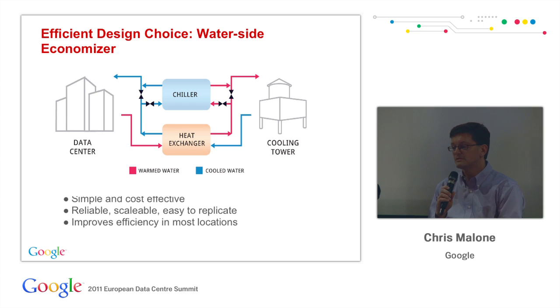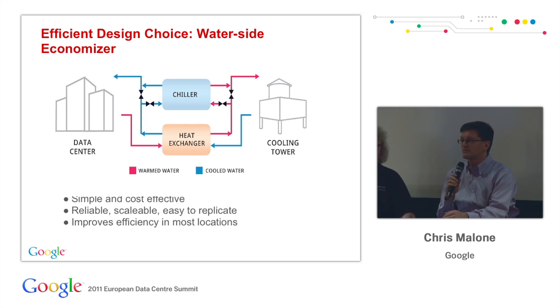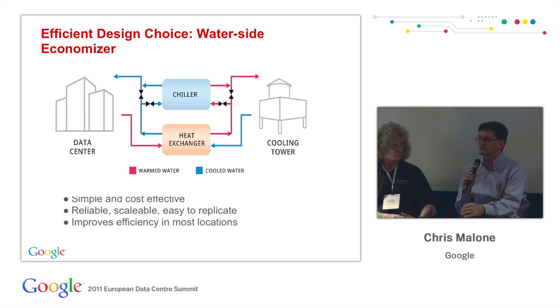So you enhance that effectiveness, or reduce the amount of chiller time, by increasing temperature—again, something James pointed out that we definitely agree with. A design like this that enables economization can be used with an evaporative cooling tower or with an air-cooled tower as well, so it's an option that's flexible depending on what resource you have at your given site.